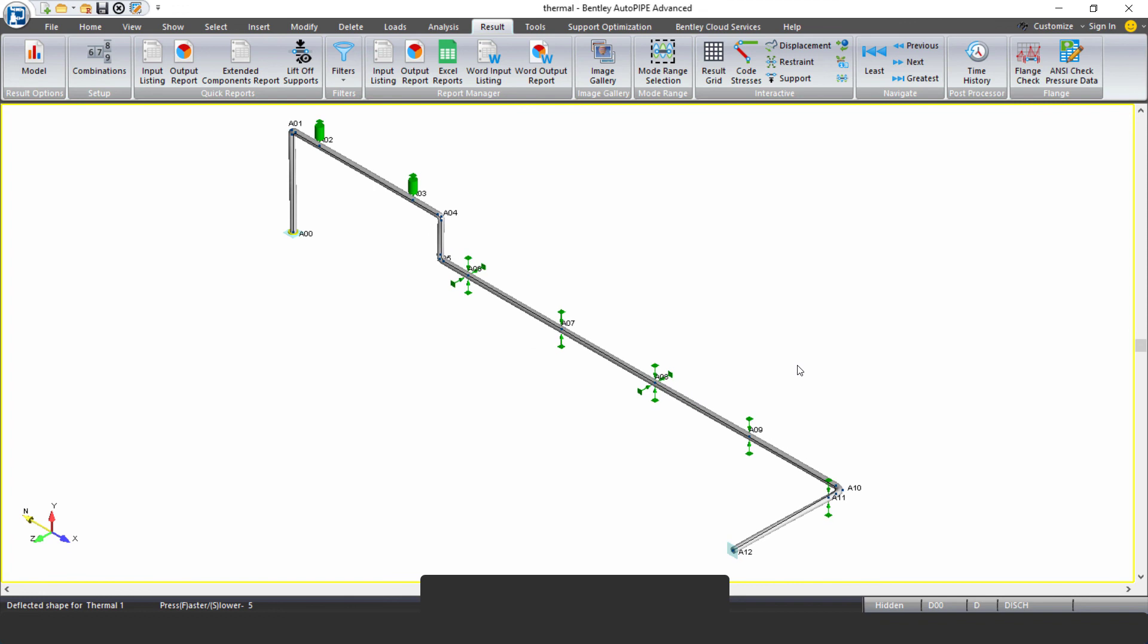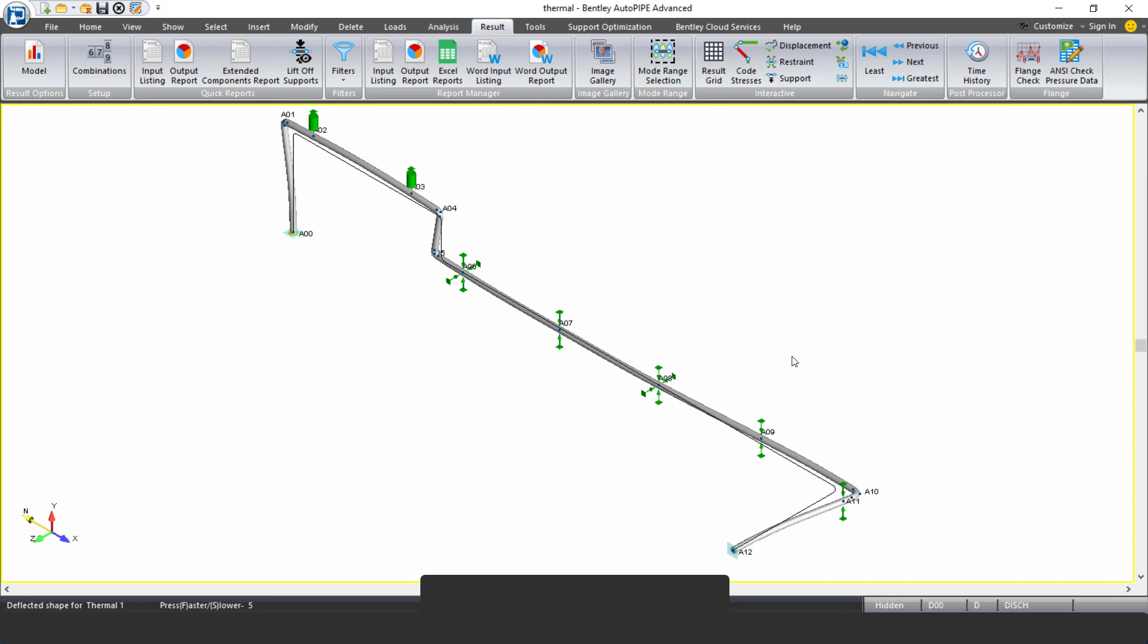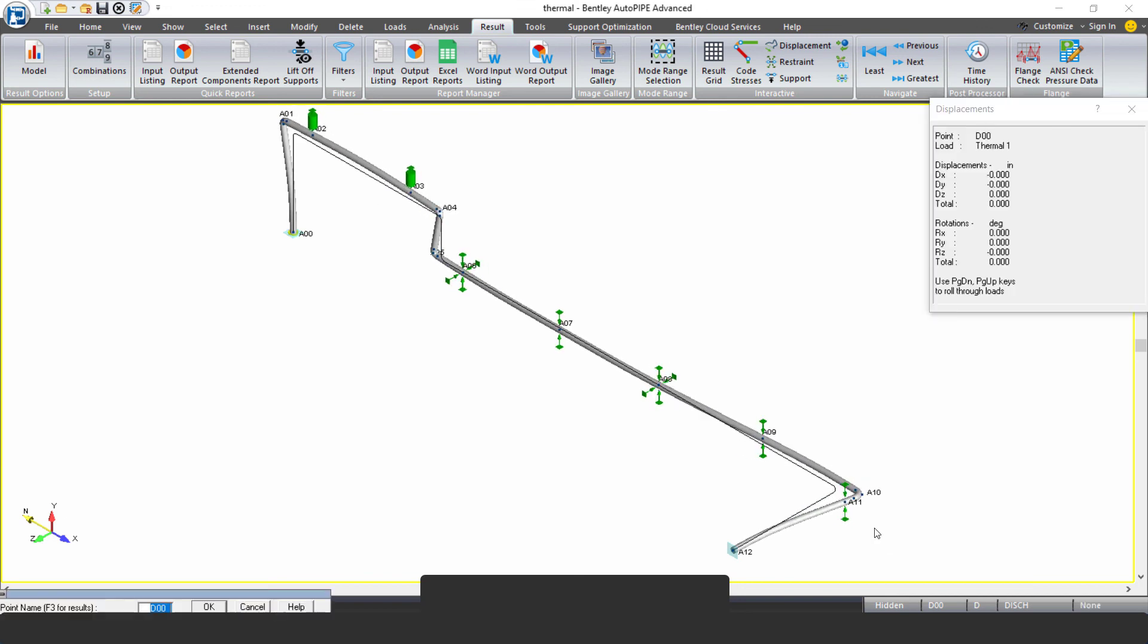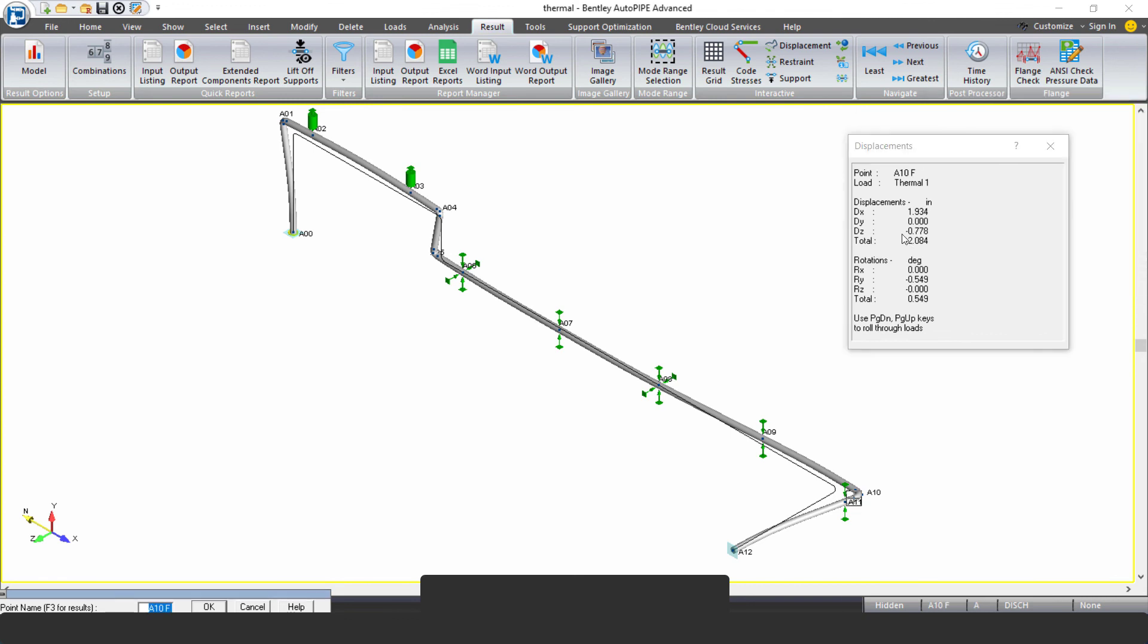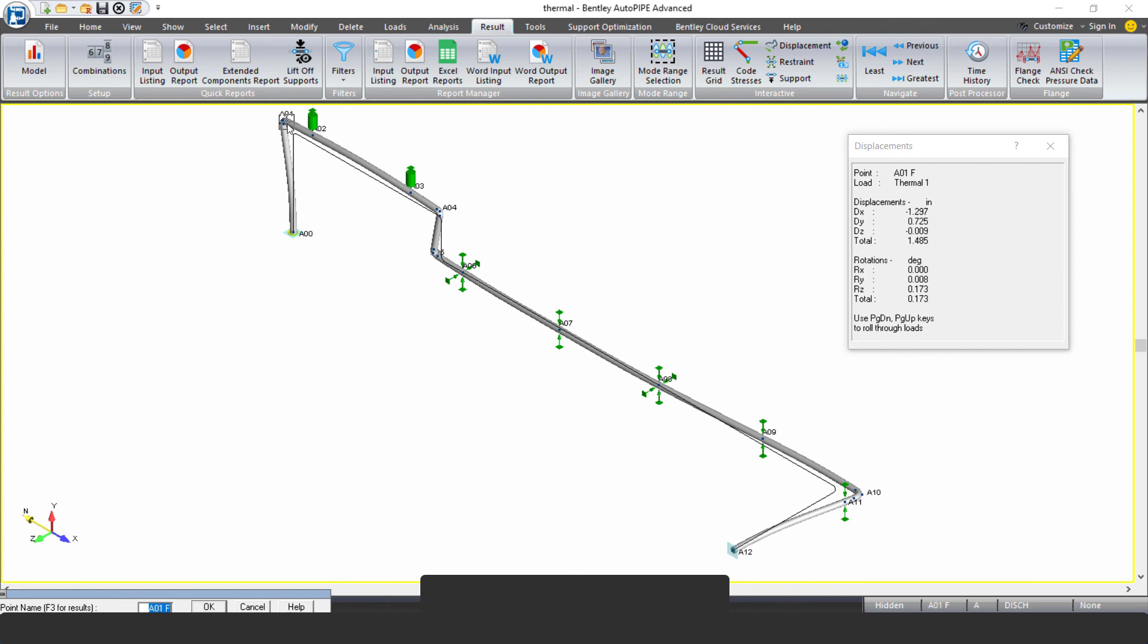and we review our results. Let's take a look at our displacement in the thermal case. And what we see is exactly that growth that we talked about, that the thermal growth is finding a way, the path of least resistance to grow, to expand as it goes from 70 degrees Fahrenheit to 500 degrees Fahrenheit. So this is an exaggerated plot in AutoPipe, but we can look at actual numbers here using our dialogue. And we can see the main growth is about two inches in the x direction, about one inch in the z direction. So again, growth in this direction, growth in this direction, based on the fact that nothing is stopping it from moving in that direction. We have growth over here, up by this spring, some vertical and x direction growth. So the springs allow the pipe to move up, which is great because we have an anchor right here. So that's good. And we have the axial growth along this long x direction line as well.